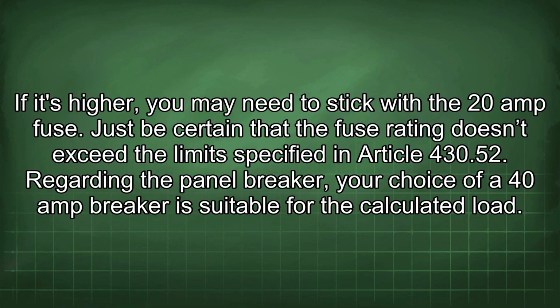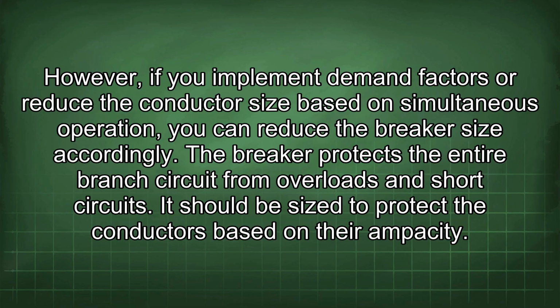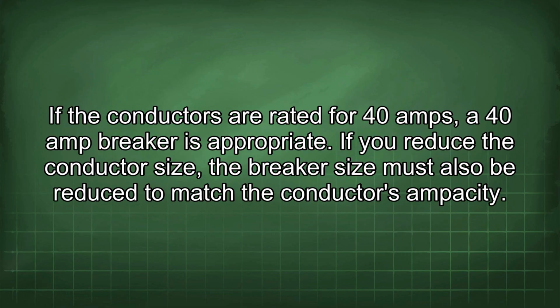Regarding the panel breaker, your choice of a 40 amp breaker is suitable for the calculated load. However, if you implement demand factors or reduce the conductor size based on simultaneous operation, you can reduce the breaker size accordingly. The breaker protects the entire branch circuit from overloads and short circuits. It should be sized to protect the conductors based on their ampacity. If the conductors are rated for 40 amps, a 40 amp breaker is appropriate. If you reduce the conductor size, the breaker size must also be reduced to match the conductor's ampacity.